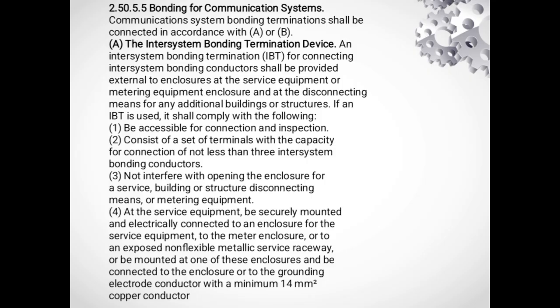Number 1. Be accessible for connection and inspection. Number 2. Consist of a set of terminals with the capacity for connection of not less than 3 inter-system bonding conductors. Number 3. Not interfere with opening the enclosure for a service, building or structure disconnecting means or metering equipment. Number 4. At the service equipment, be securely mounted and electrically connected to an enclosure for the service equipment, to the meter enclosure, or to an exposed non-flexible metallic service raceway, or be mounted at one of these enclosures and be connected to the enclosure or to the grounding electrode conductor with a minimum 14 mm squared copper conductor.